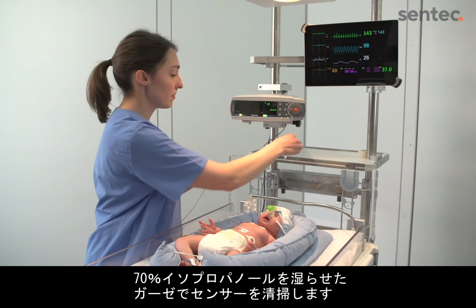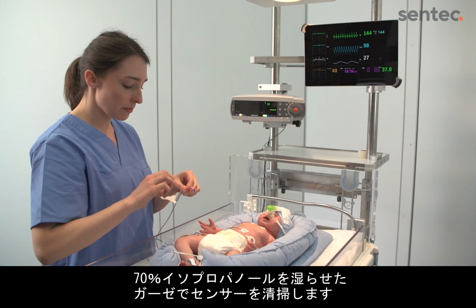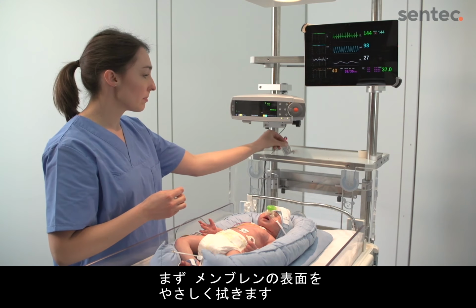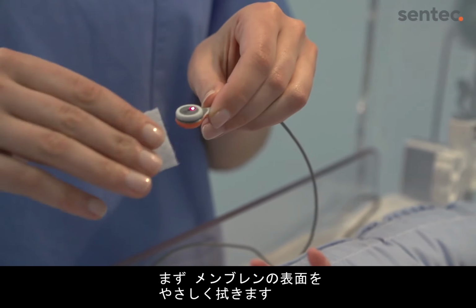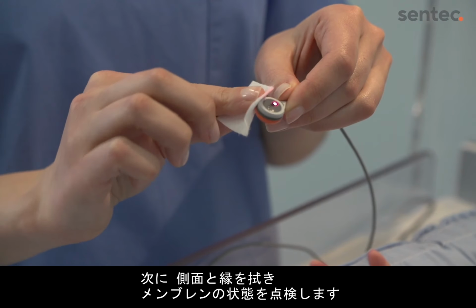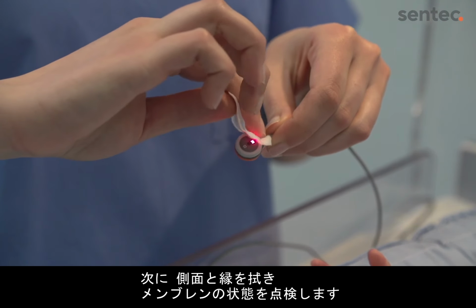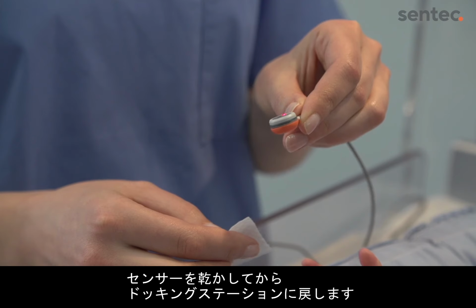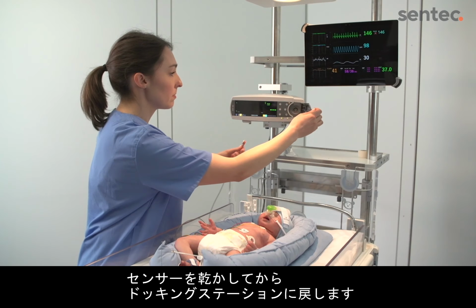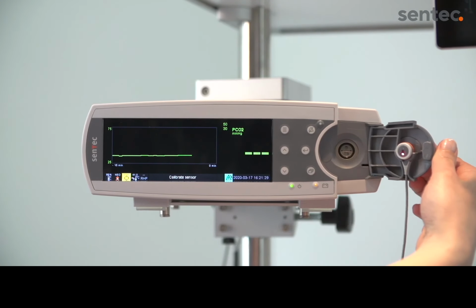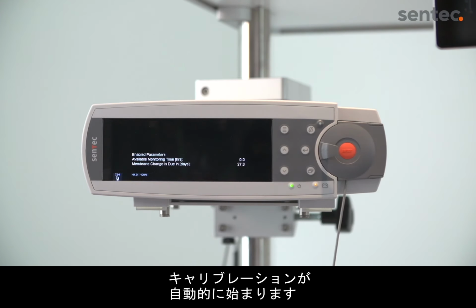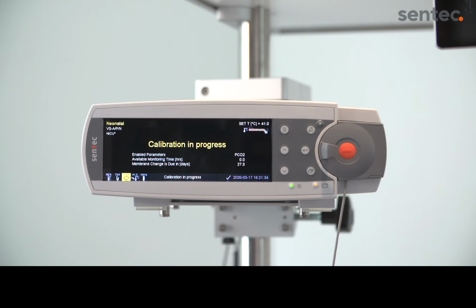Gently clean the sensor using a gauze soaked with 70% isopropanol. First, gently wipe the membrane surface. Then, clean the sides and outer rim and inspect the condition of the sensor membrane. Allow the sensor to dry before inserting it into the docking station. Once the docking station door is closed, the monitor will automatically begin calibration.